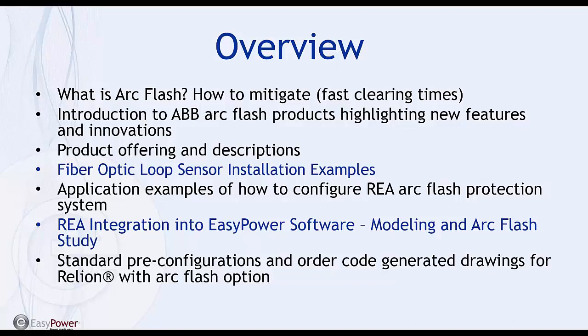We'll superimpose the REA Arc Flash system right on the EasyPower one line, and I think it'll be very clear how the selectivity is accomplished and how the modeling is set up in the software. Also, to conclude, we'll talk about our ReliOn line of relays, where you have the Arc Flash option built in, and you have the standard pre-configurations and order-coded generated drawings already completed for you based on order code selection.